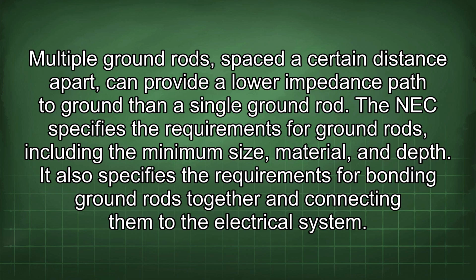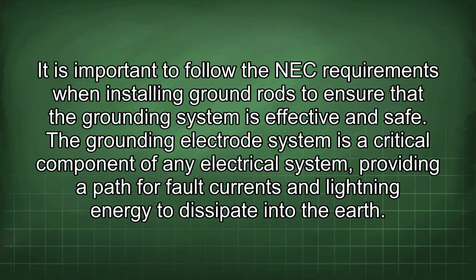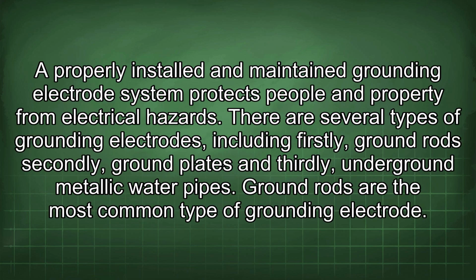It also specifies the requirements for bonding ground rods together and connecting them to the electrical system. It is important to follow the NEC requirements when installing ground rods to ensure that the grounding system is effective and safe. The grounding electrode system is a critical component of any electrical system, providing a path for fault currents and lightning energy to dissipate into the earth. A properly installed and maintained grounding electrode system protects people and property from electrical hazards.